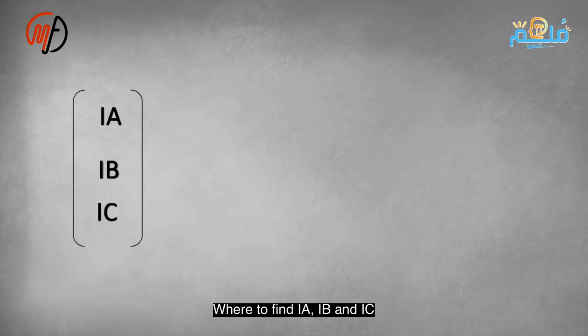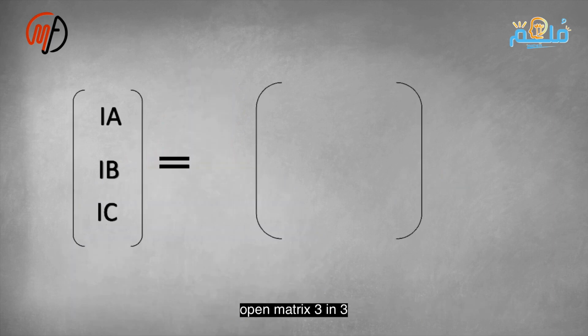Symmetrical components help identify the fault type via positive, negative, and zero sequences without knowing the fault current. If only the positive sequence is present, it indicates a symmetrical fault.